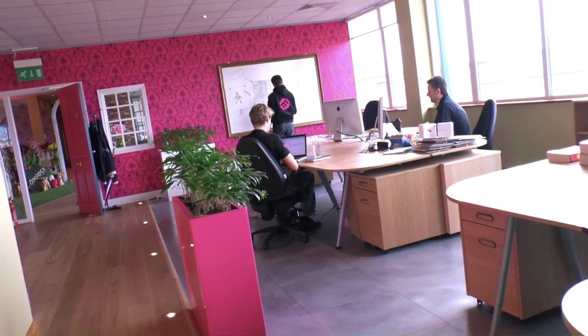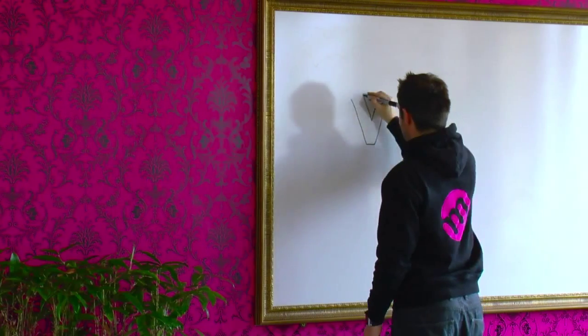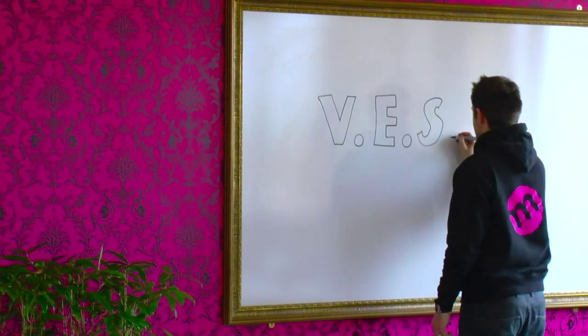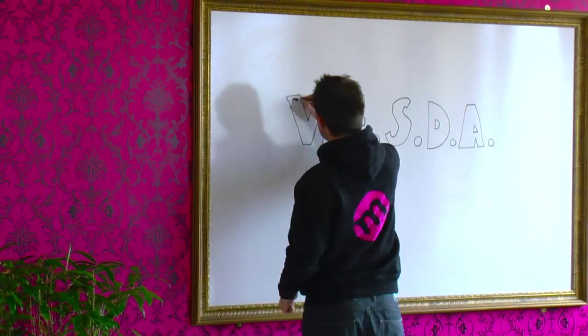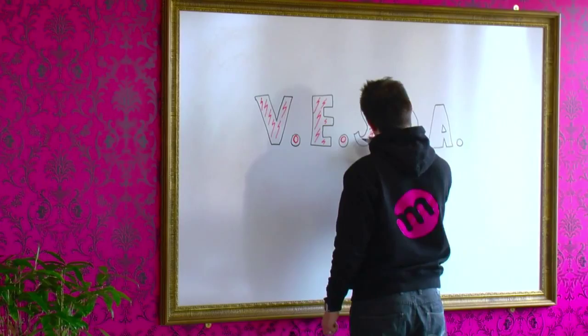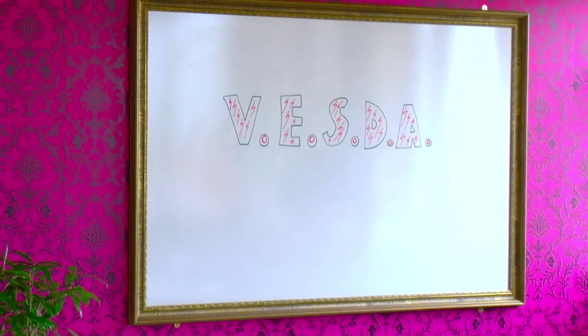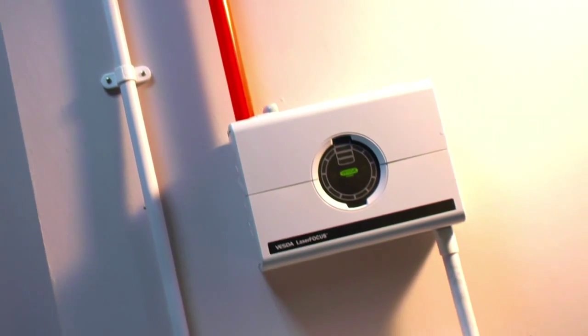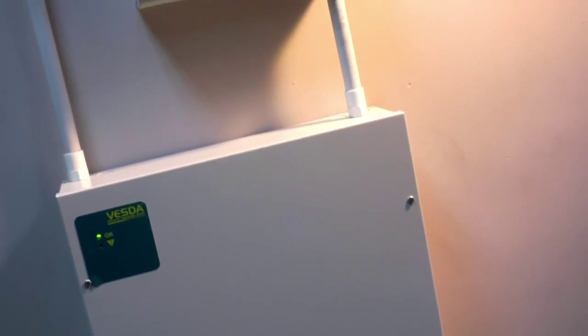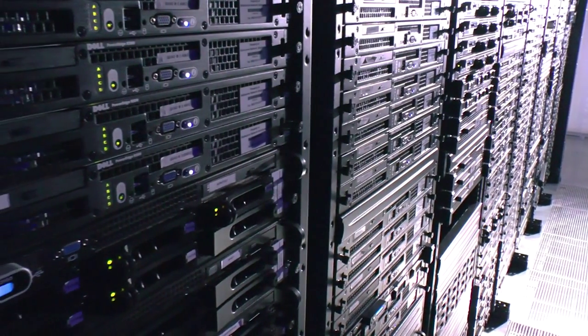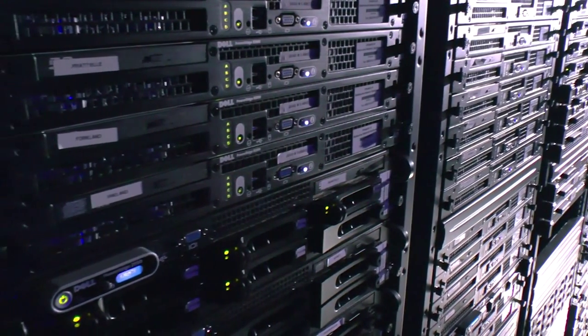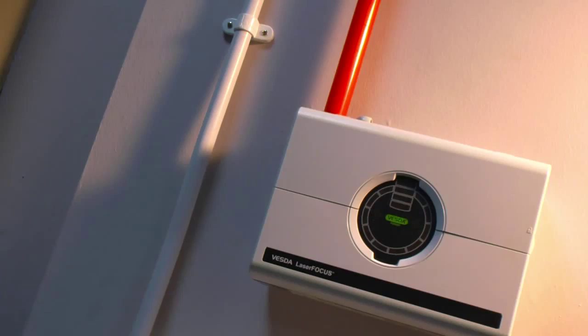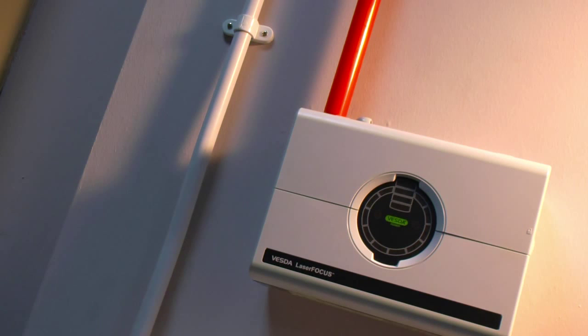With so much electrical equipment in one room, the risk of fire is taken extremely seriously. We have multiple layers of fire protection. First of all, we have what's called a VESDA, which stands for Very Early Smoke Detection Apparatus. You can see part of this above the air conditioners in the form of red tubes, which sample air from the room back to the VESDA system. This shines a laser through the sampled air continually, and it will detect even the smallest trace of smoke before you can even see it or smell it. The idea being that this is an early warning system alerting us to a problem.